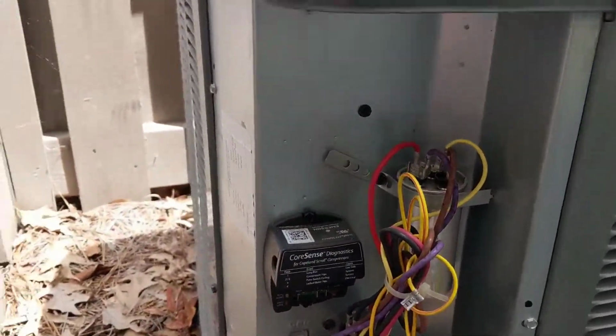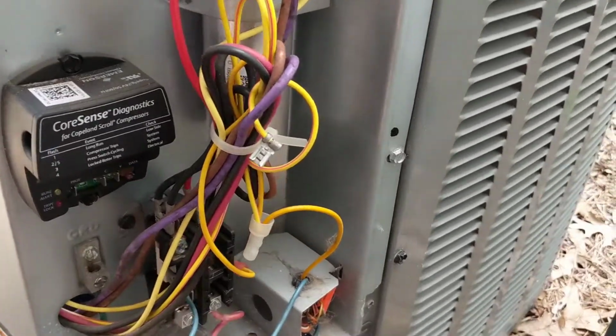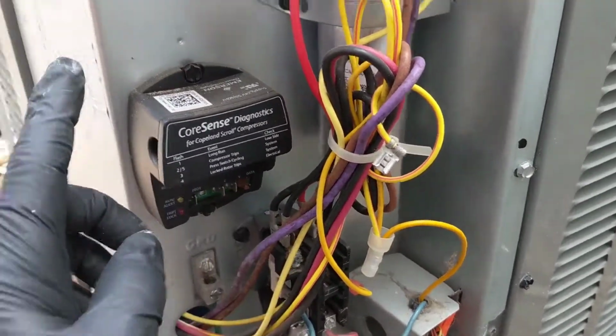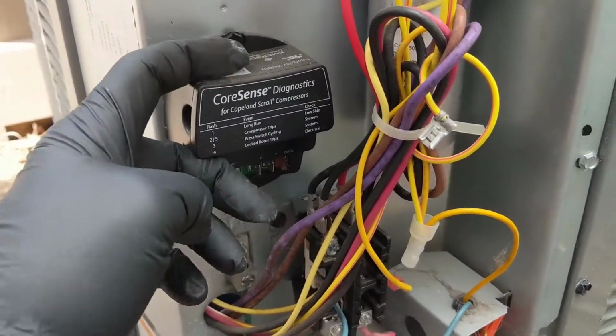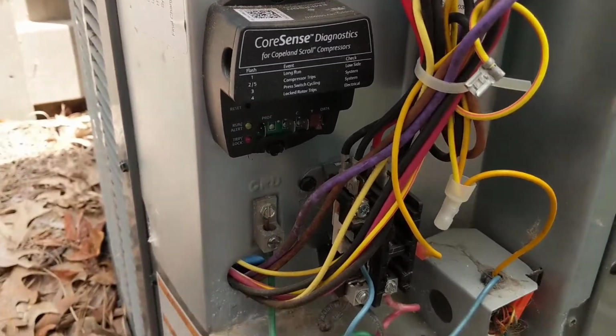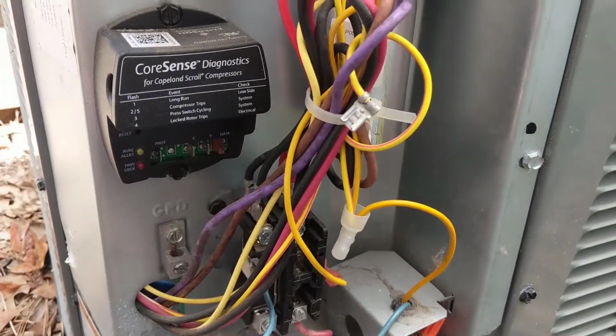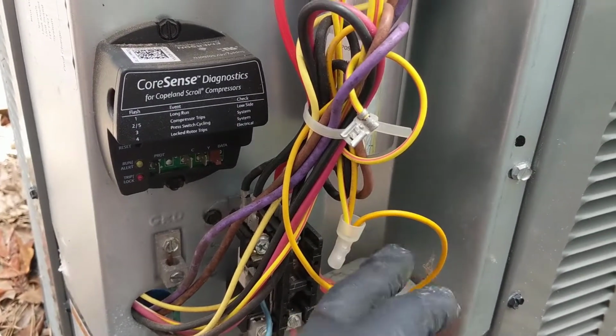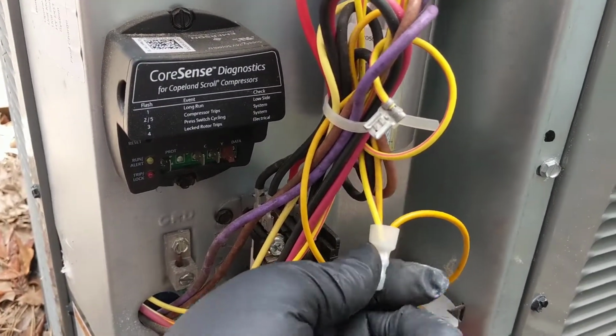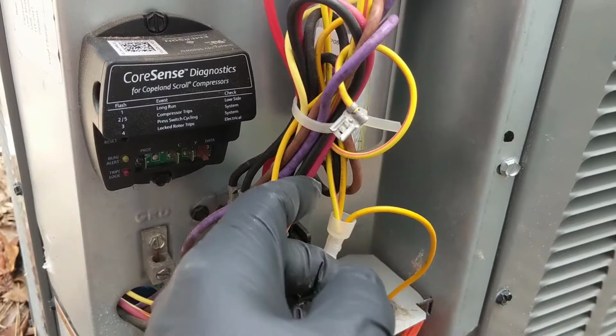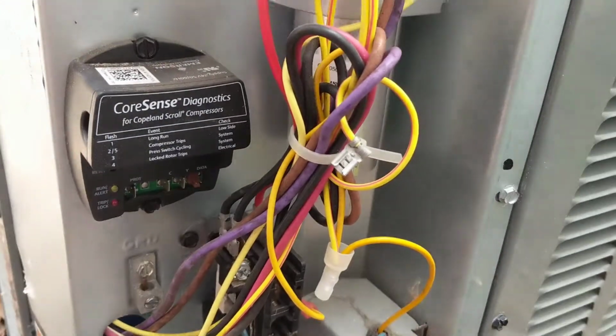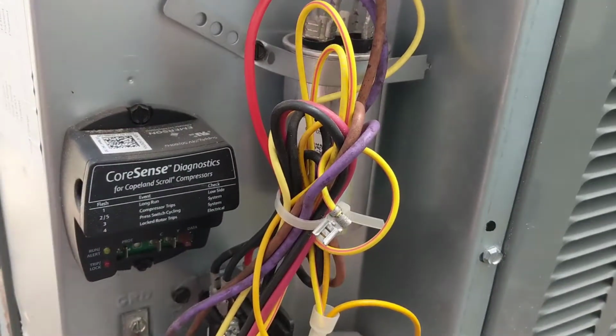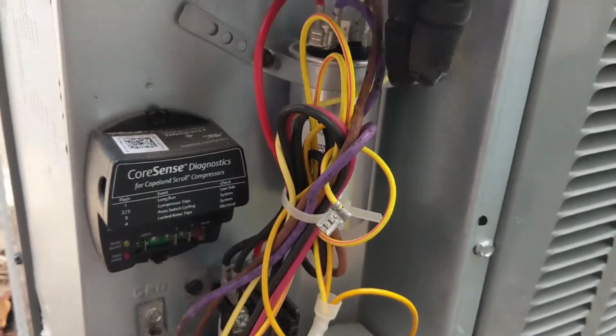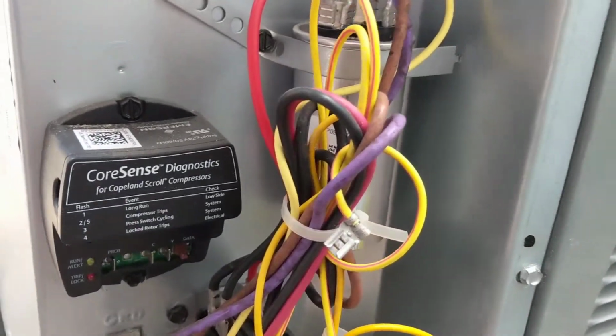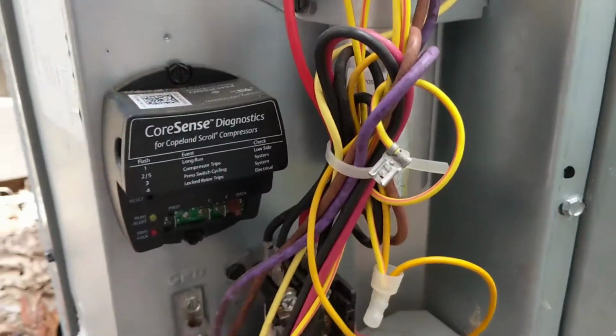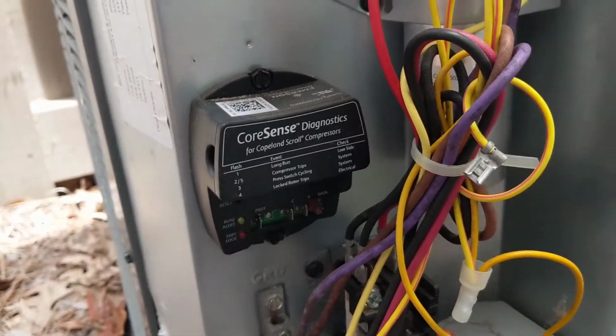Well, I got the unit up and running now, and I believe I knew what the problem was. This CoreSense diagnostic here, somebody has everything unhooked from it, and the yellow wire coming out here, the 24 volts, goes to this wire nut, and the yellow with the red stripe is this terminal right there. Well, when I pulled the cabinet door open, it was up against the metal of the cabinet, so that's definitely what blew the 3 amp fuse there in the board.